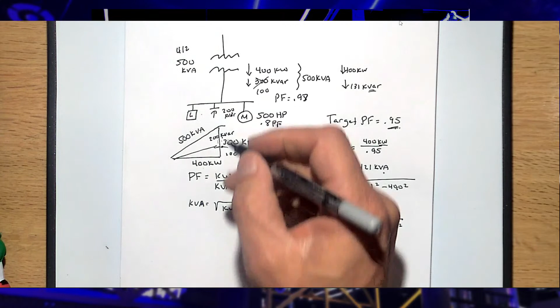And as far as the protective devices downstream, a lot of times when you build a system, the cables and the breakers are set up for that size. So you could relieve some of the capacity, but that's kind of the point. Yeah, and you still have to protect the conductor at its ampacity, so you're not going to change that out. But like you said, I can put additional load on that transformer, maintaining a lower kVA based on my usage.